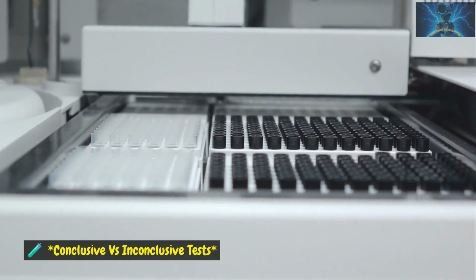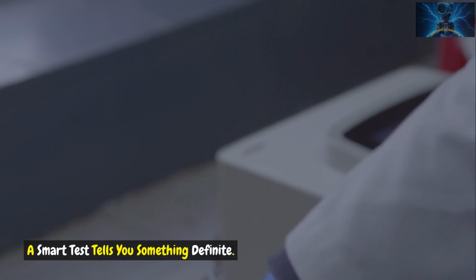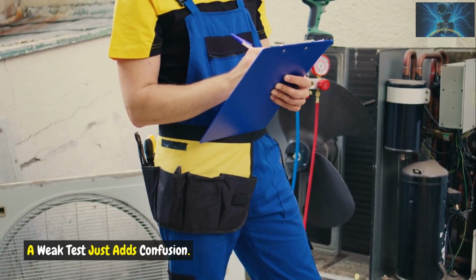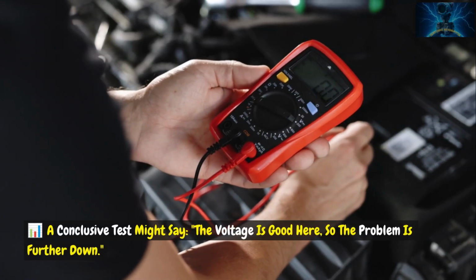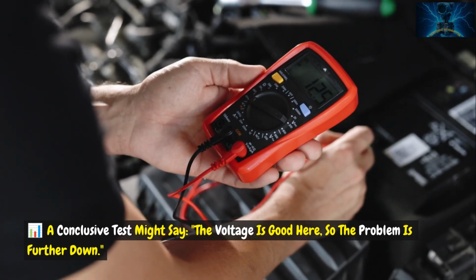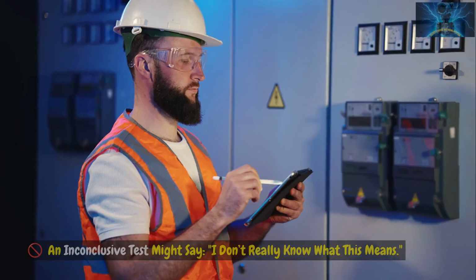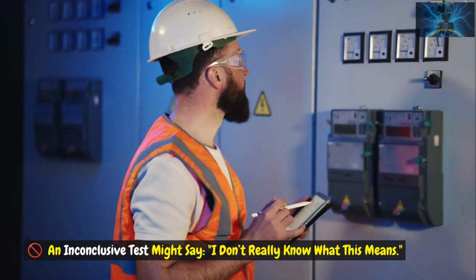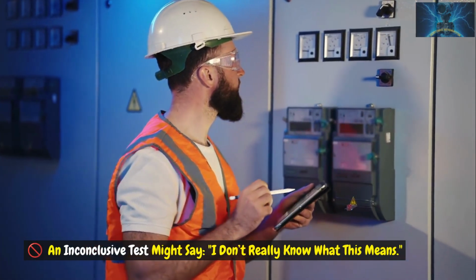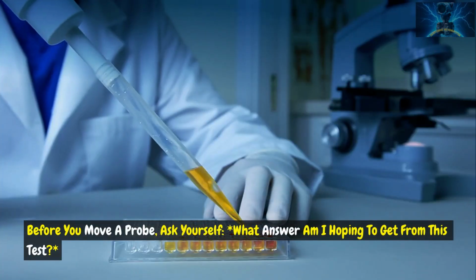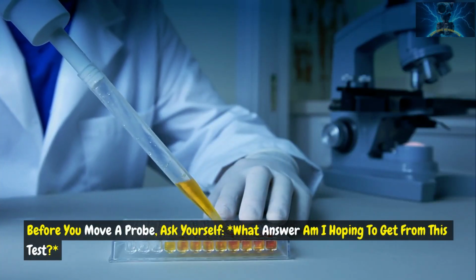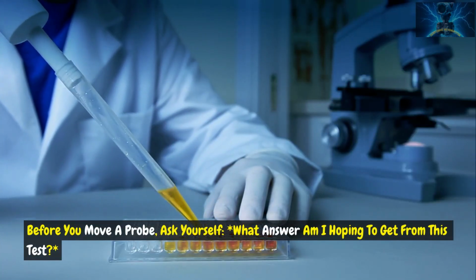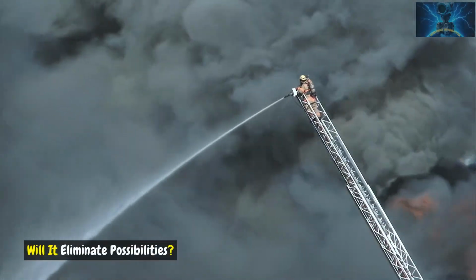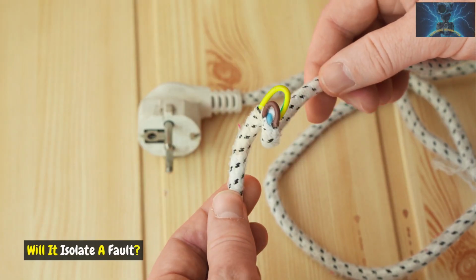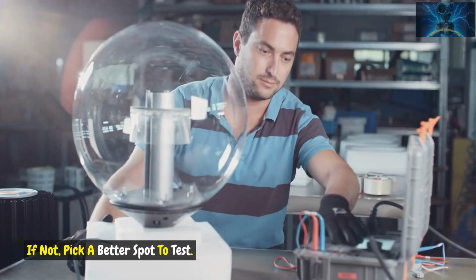Conclusive versus inconclusive tests. A smart test tells you something definite. A weak test just adds confusion. A conclusive test might say, the voltage is good here, so the problem is further down. An inconclusive test might say, I don't really know what this means. Before you move a probe, ask yourself, what answer am I hoping to get from this test? Will it eliminate possibilities? Will it isolate a fault? If not, pick a better spot to test.